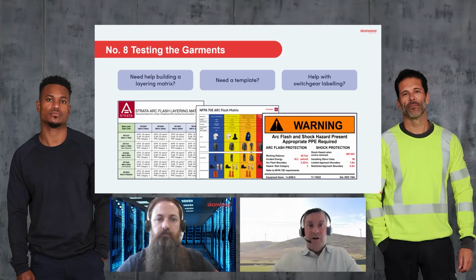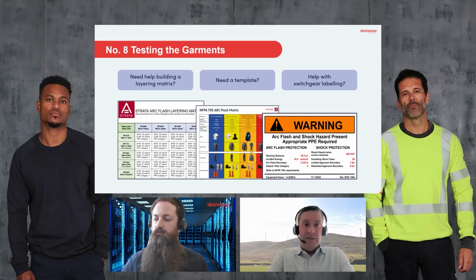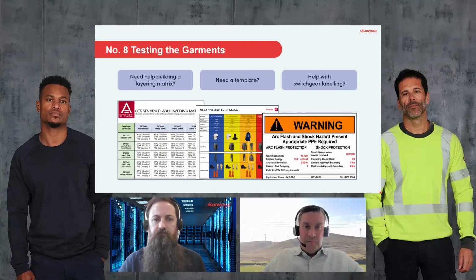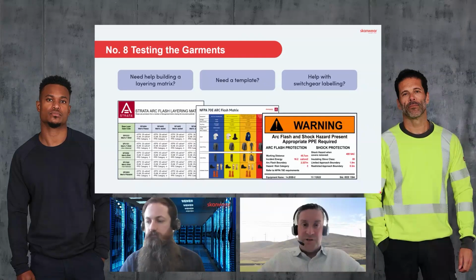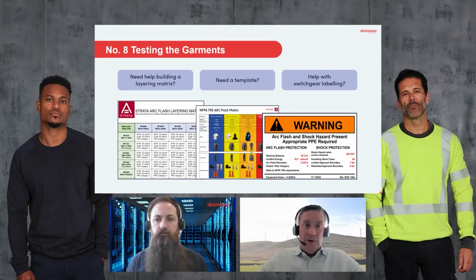If you've got a large site or a lot of facilities and can't afford or haven't got time to put in place an energy study, that might be your end goal. But for something more immediate, NFPA 70E and CSA Z462 both have category methods that pick up normal information from switchgear panels and give you an idea of what PPE to wear, always on the conservative side, so you'd be well protected.